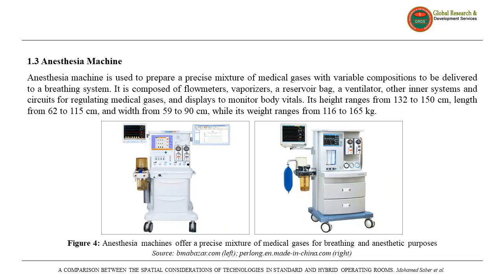Another important element inside the operating room is the anesthesia machine. It's used to provide oxygen for patient ventilation and precisely mixes the required anesthetic gases. With its different models and designs, it's located near the patient's side or feet and has a height between 132 and 150 centimeters, length between 62 and 115 centimeters, and width between 59 and 90 centimeters.